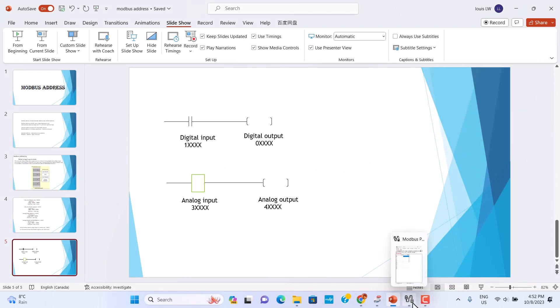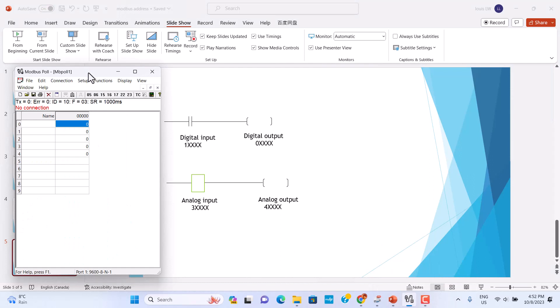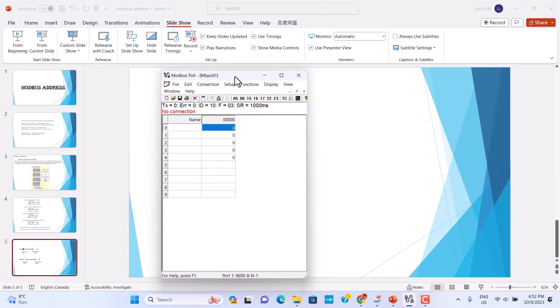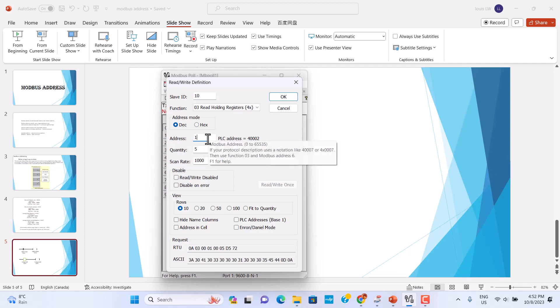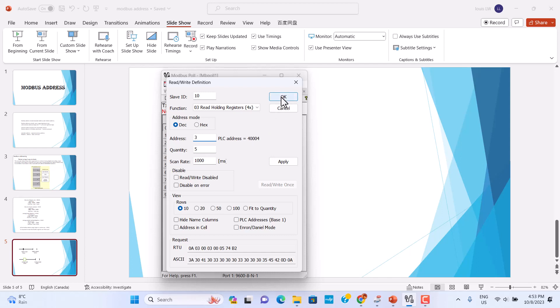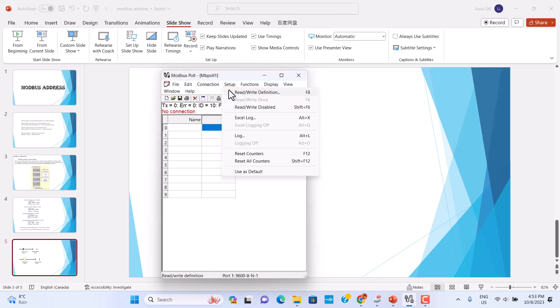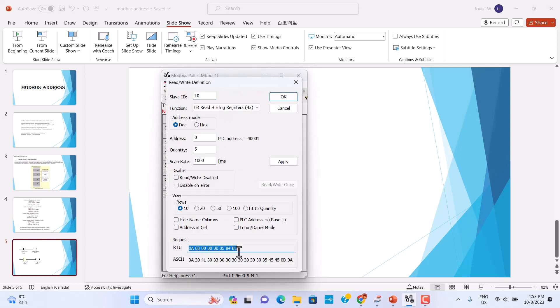When using addresses — for example when troubleshooting a Modbus device — it is very simple. You can use a setup read tool. Here you can see two types: relative address and absolute address. For example, if the PLC address is 40002, the relative address changes accordingly. That is why when using function code you use the relative address, but when troubleshooting you will use the absolute address. This display uses hexadecimal numbers.